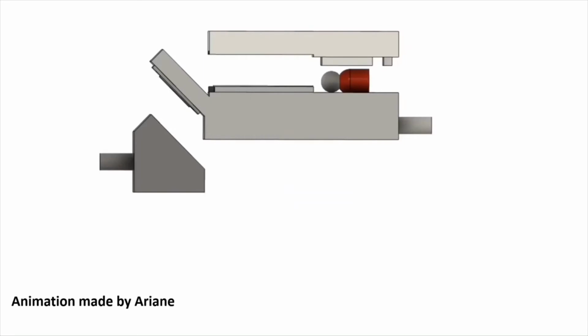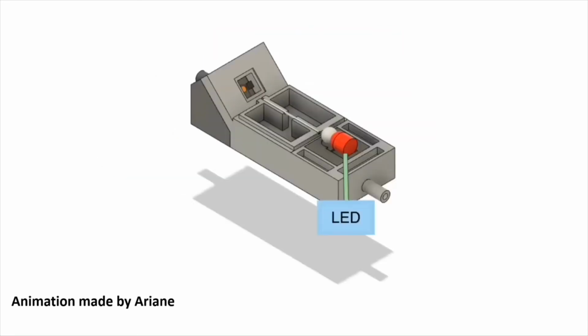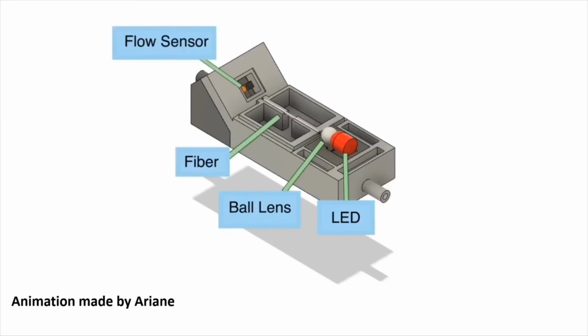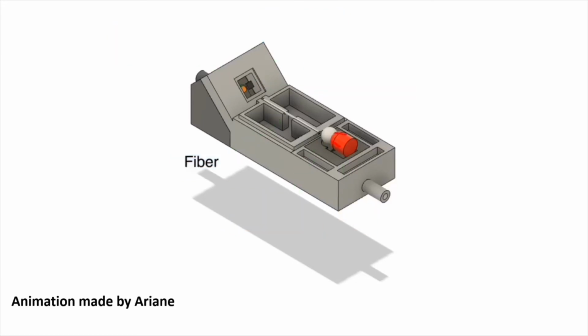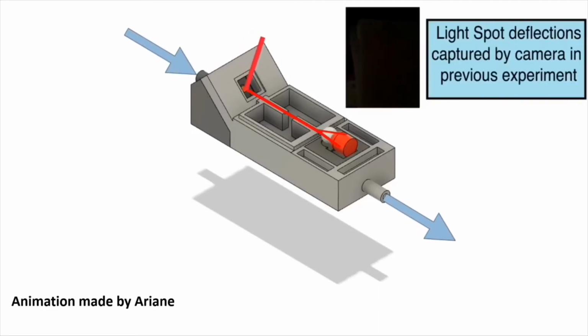The optical system shown here focuses a light spot onto the sensor, which reflects that light at varying angles. This light deflection is measured by a photodiode embedded in a PDMS cover above the sensor tip. Here you can see how light enters the ball lens from the LED and is focused onto the fiber. It then deflects off of the sensor tip. As flow increases, the sensor deflection increases and the light is deflected at a larger angle, and vice versa.